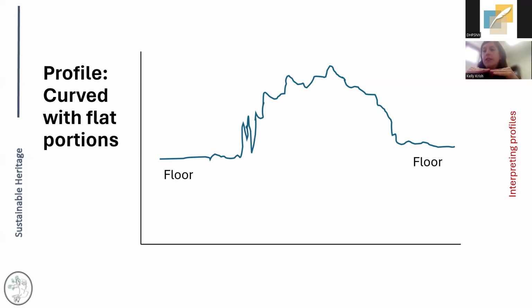So it's maintaining a floor that it can't drop below. So this would imply that there's humidification present. It's keeping that floor up, it's humidifying, and it's maintaining that line. What you're not seeing is a flat line in the summer, and it's kind of going along with whatever would be happening outside. So we know we don't have any dehumidification. It's just going along with maybe there's some buffering from the building, but it's largely reflective of outside conditions.